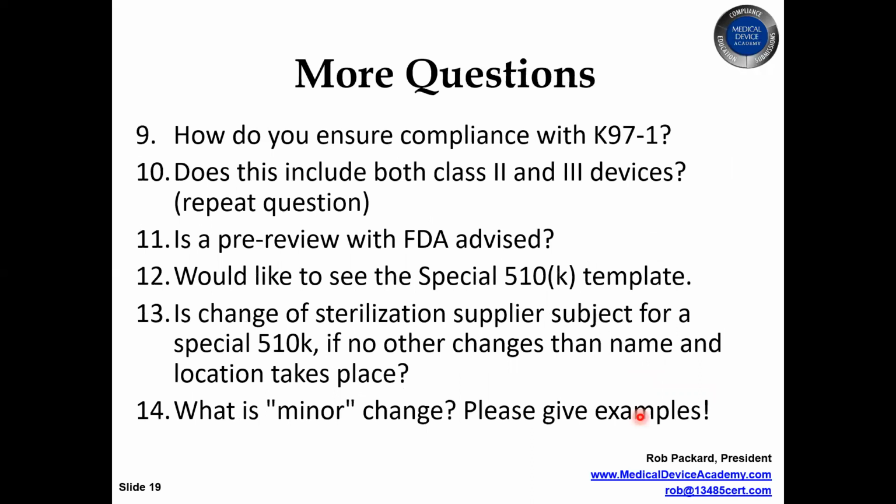And actually, Mary Votter, one of my employees, she's a biomedical engineer, converted that entire flowchart into a form that you fill out, asking all the same questions. And if you fill out that form and use that as a letter to file, it will determine whether you need a 510K or not. So that's how you ensure compliance. You go through that letter to file template and answer that. And I emailed that to everybody that got the slide deck.